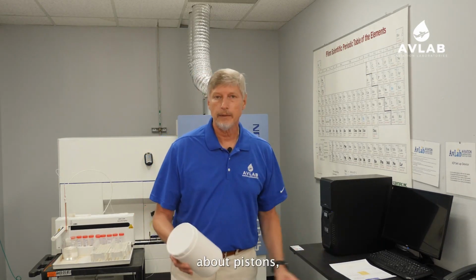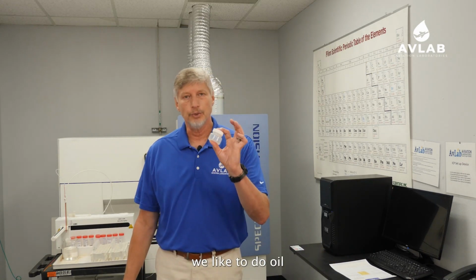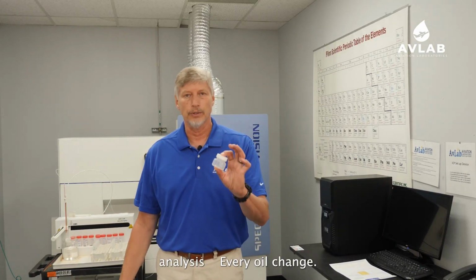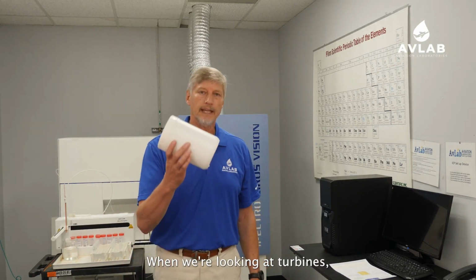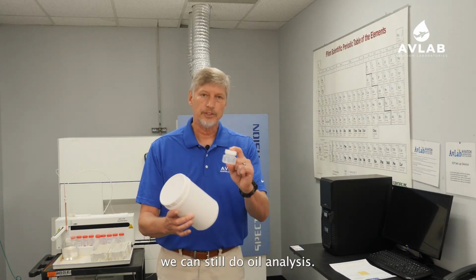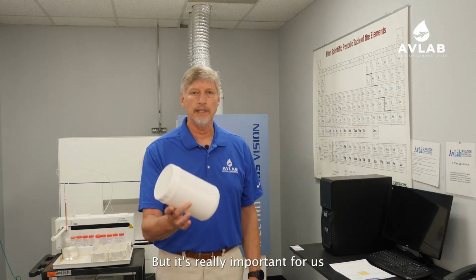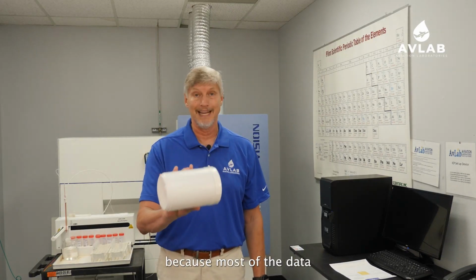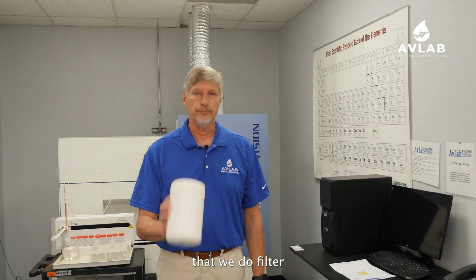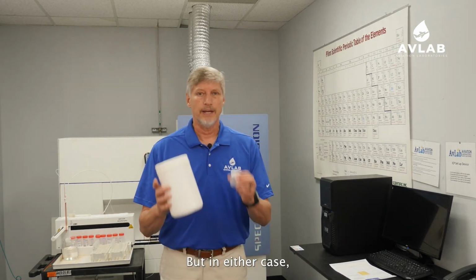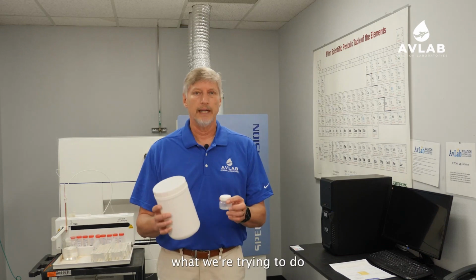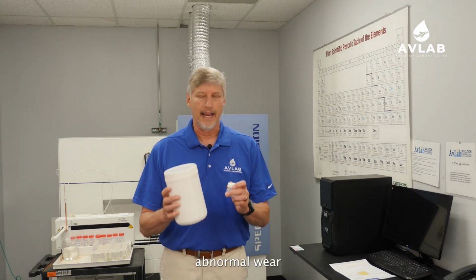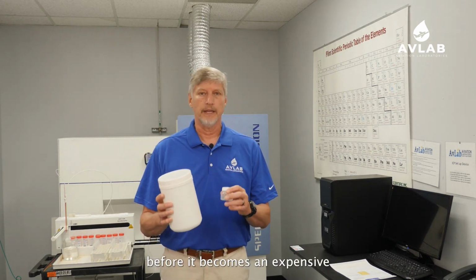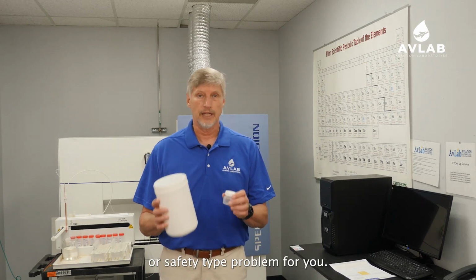So when we're talking about pistons, we like to do oil analysis every oil change. When we're looking at turbines, we can still do oil analysis, but because most of the data is in the filter, it's really important that we do filter analysis as well. But in either case, what we're trying to do is identify abnormal wear before it becomes an expensive or safety type problem for you.